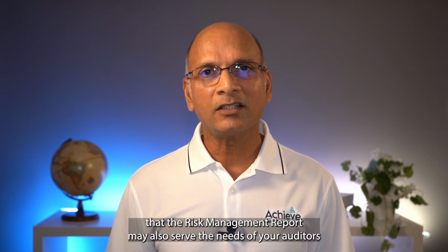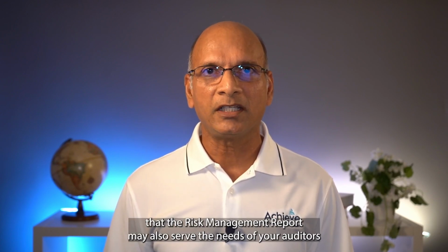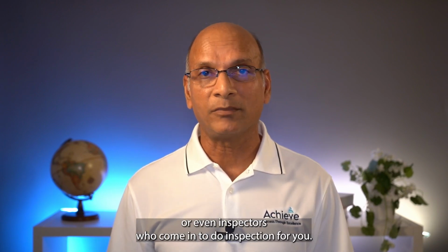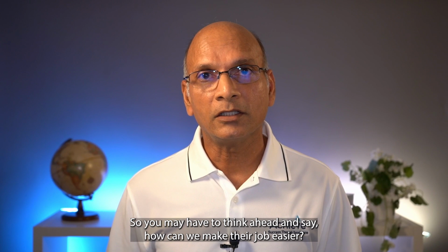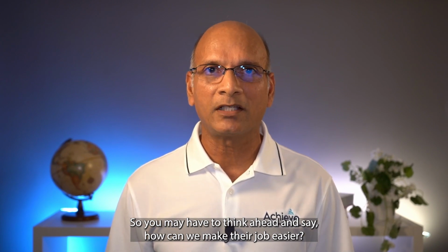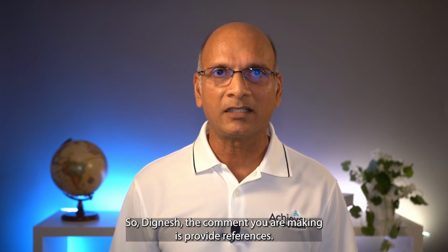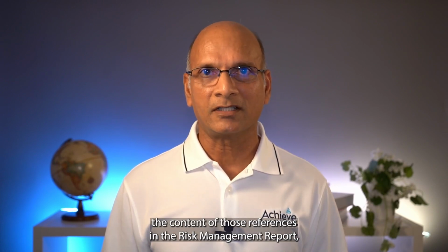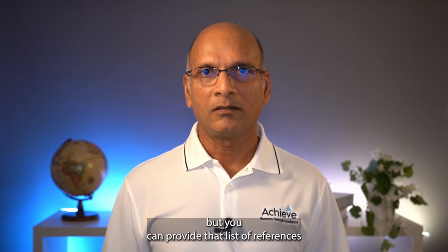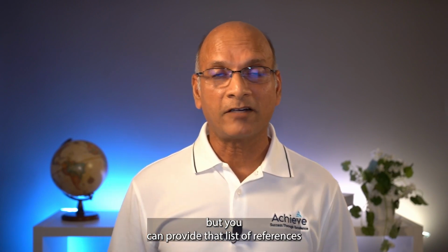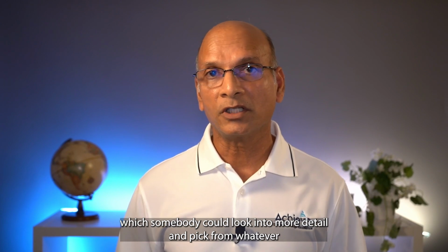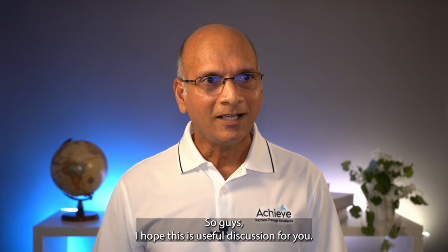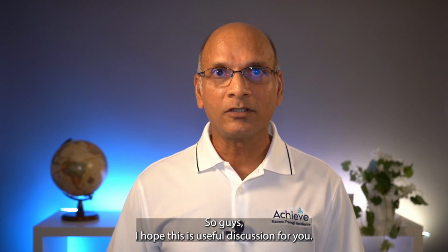So keep in mind that the risk management report may also serve the needs of your auditors, or your notified body auditors, or even inspectors who come in to do inspection for you. So you may have to think ahead and say, how can we make their job easier? So Dignesh, the comment you are making is to provide references. You don't have to include the content of those references in the risk management report. But you can provide that list of references which somebody could look into in more detail and pick from, whatever they want to pursue. So guys, I hope this is a useful discussion for you.